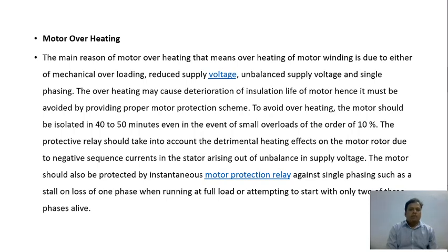So the overheating may cause deterioration of the insulation life of motors, and hence it must be avoided by providing a proper motor protection scheme. Deterioration of insulation life is also one of the conditions, and hence it must be avoided by providing a proper motor protection scheme. To avoid this overheating, the motor should be isolated in 40 to 50 minutes even for small overloads of the order of 10%.